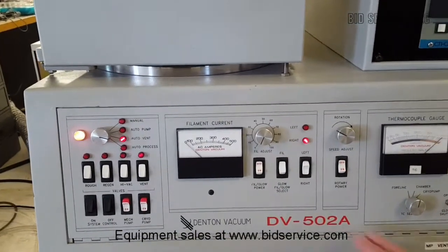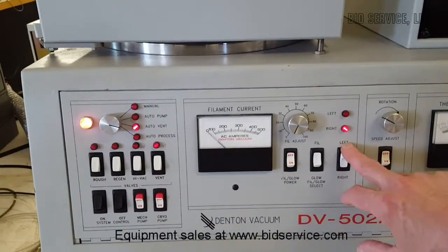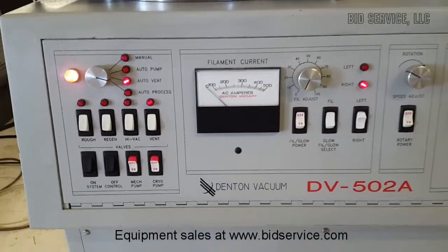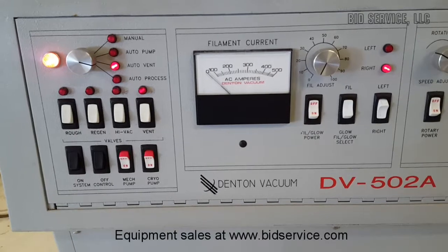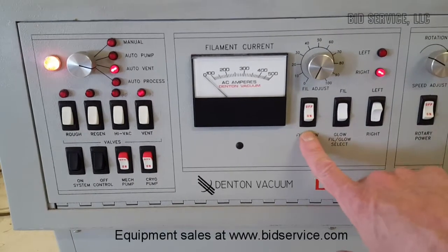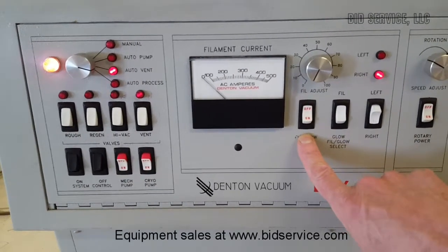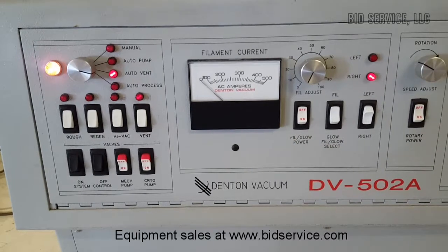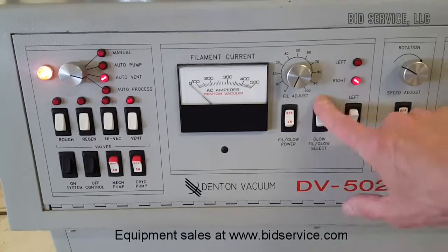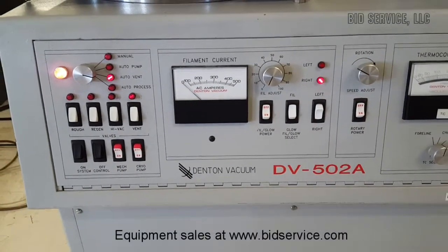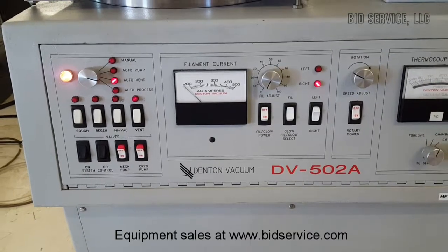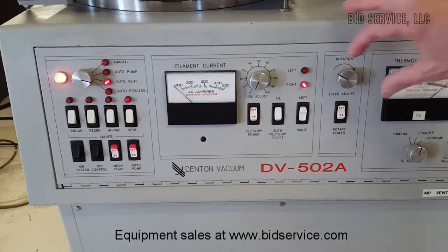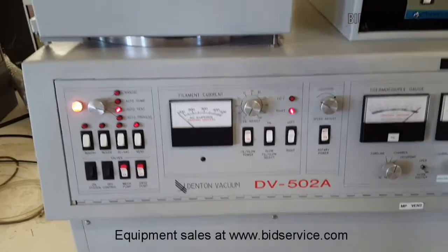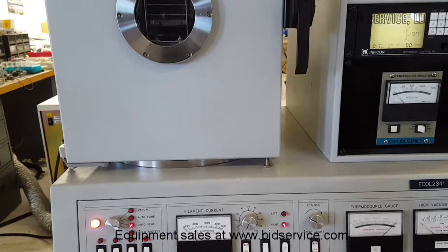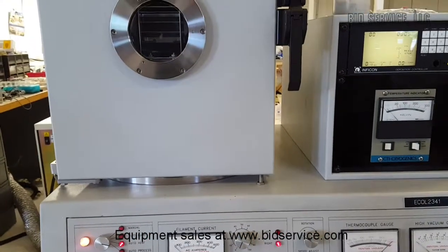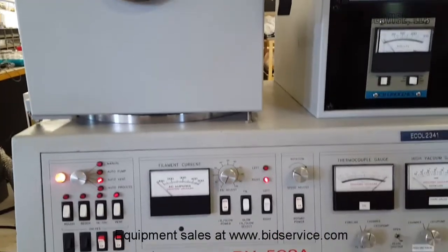And just a few other things that you can run in manuals. You have a left and right select for the sources inside. I'll show you that when we open it up. You can turn your filament on here. And this is always in the filament position for this machine. And you can adjust your rotational speed. I'll show you the planetary up top that's provided with this machine. And then you also have a shutter open and close switch here too.